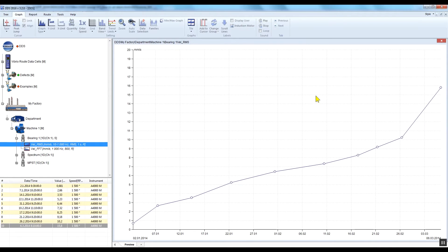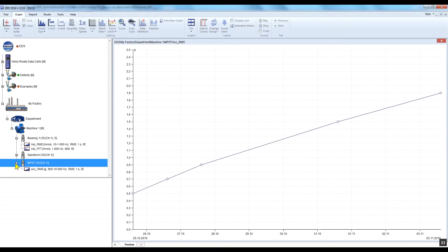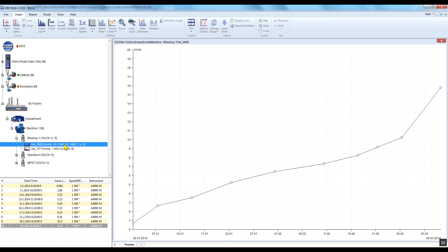The second option is to set the Adash alarm limits. They are applicable only for two types of data cells: velocity RMS in the 10 to 1000 Hz range, and acceleration RMS in the 500 to 16 kHz range. See the Vibrio manual for more information about Adash standards and their limit values.